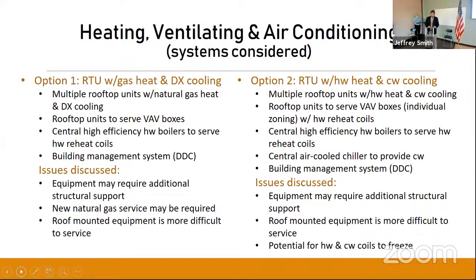One of the issues we discussed with that option: the equipment may require additional structural support, since a majority of the equipment is currently within the building, and the roof structure may not be designed to handle new rooftop equipment. So you'd be spending additional money to implement that option without really getting anything back. We may also need a new natural gas service because of the size of this building and putting all the rooftop units up there on gas — we may have to bring in a new service for that. And historically, rooftop equipment, especially in this area, is more difficult to maintain; realistically you're going to have issues with it during a snowstorm or other inclement weather.